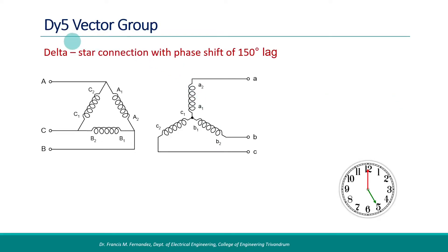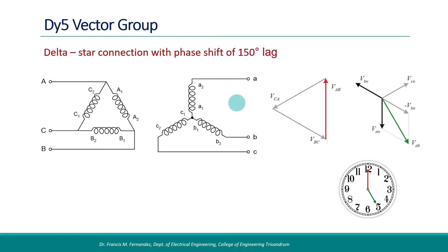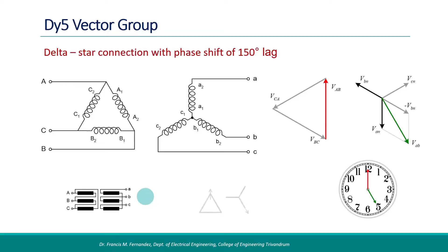In the DY5 vector group, the primary is delta connected and the secondary is star connected. Note that the polarity of the secondary side windings is changed here — the positions of A1 and A2 are interchanged. Therefore, in the phasor diagram, the voltage induced in winding A of the secondary will be 180 degrees displaced from the primary side line voltage. Similarly, the VB phasor is also displaced by 180 degrees. The line voltage VAB in the secondary is obtained by VA minus VB. The secondary line voltage is lagging by 150 degrees from the corresponding primary voltage — the 5 o'clock position holds here as well. The simplified connection diagram and displacement diagram are shown.